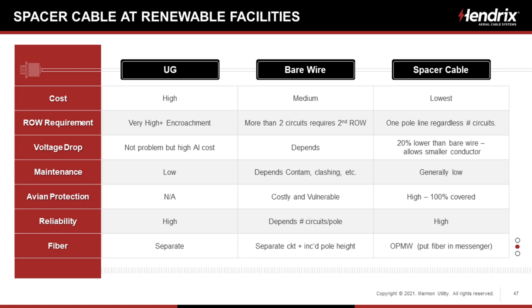And I just had a quick chart here on the pros and cons of spacer cable at renewable facilities. When we talk about cost, underground is the highest, spacer cable is the lowest. Right-of-way requirement, spacer cable is the best. Voltage drop, spacer cable should be the best. Underground is no problem since you're buying so much aluminum that you don't have much of a voltage drop.